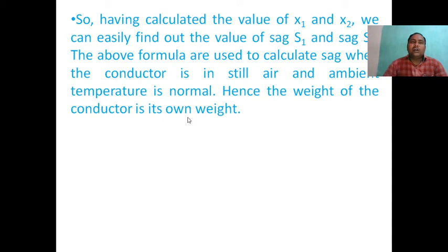When the supports are at equal heights, sag S is equal to WL square by 8T. When the supports are at unequal levels, we can calculate x1 and x2 values. From that, we can easily calculate the sag.